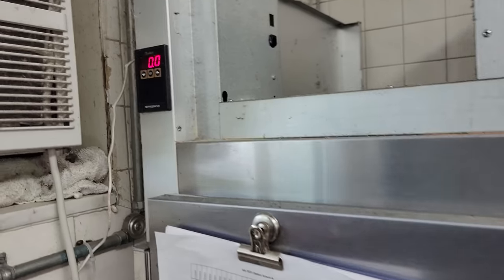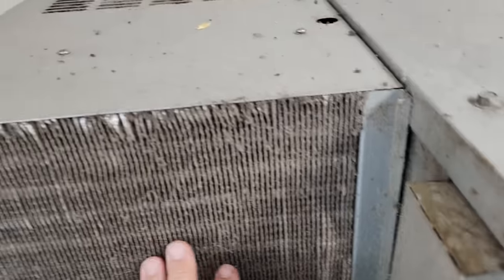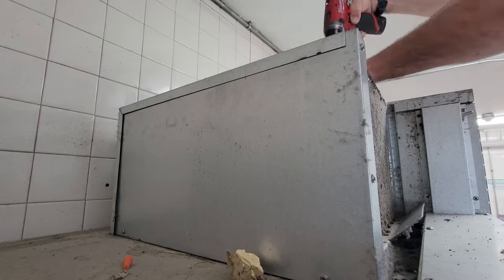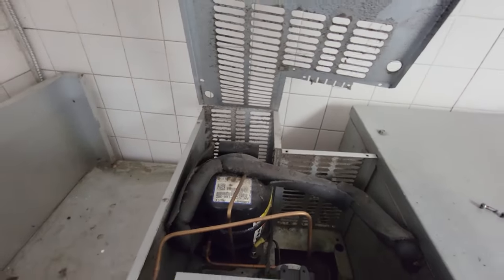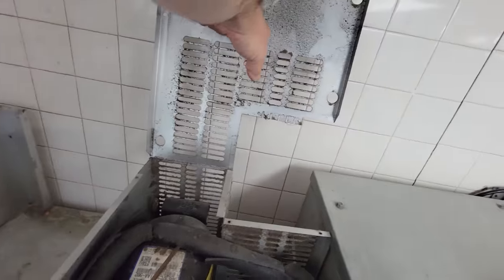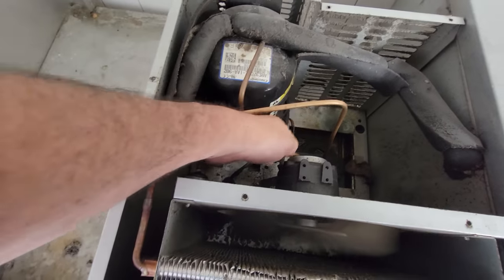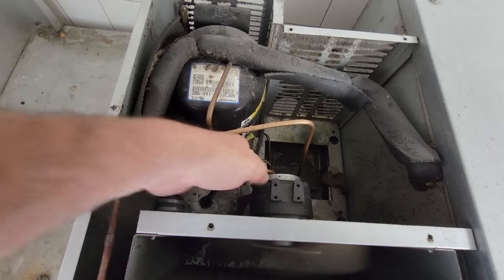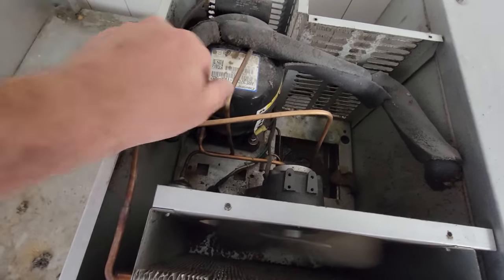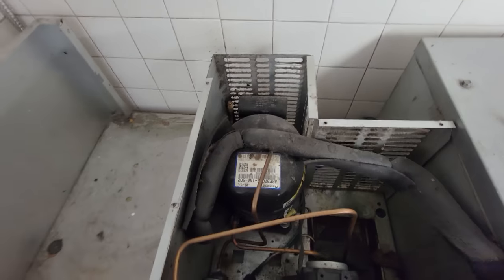It says zero degrees there. Compressor's really, really hot. Discharge line is a little bit warm — could be temperature coming from the compressor. Let's go ahead and hook onto a suction and see if it's off on thermal or if it's just low on charge.